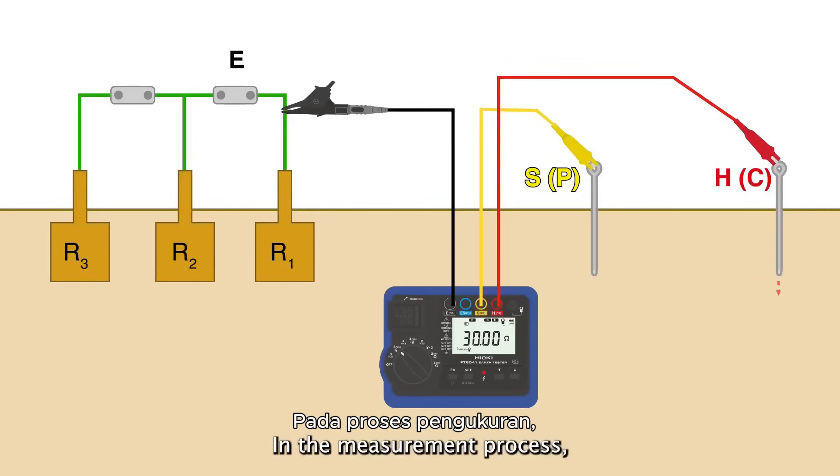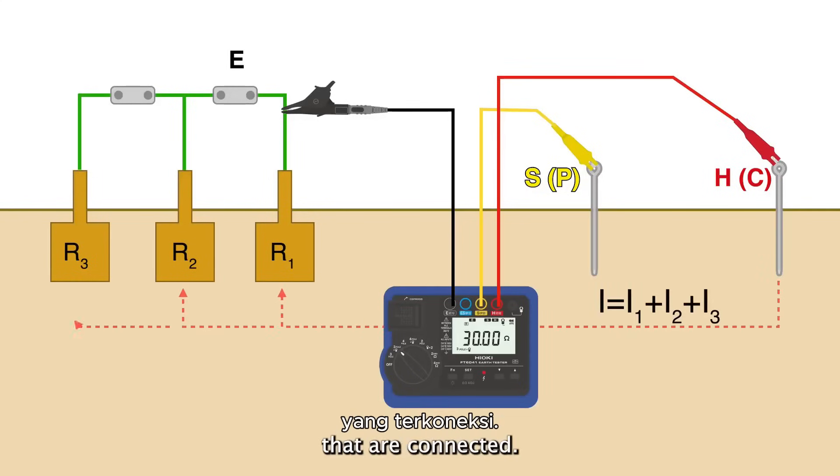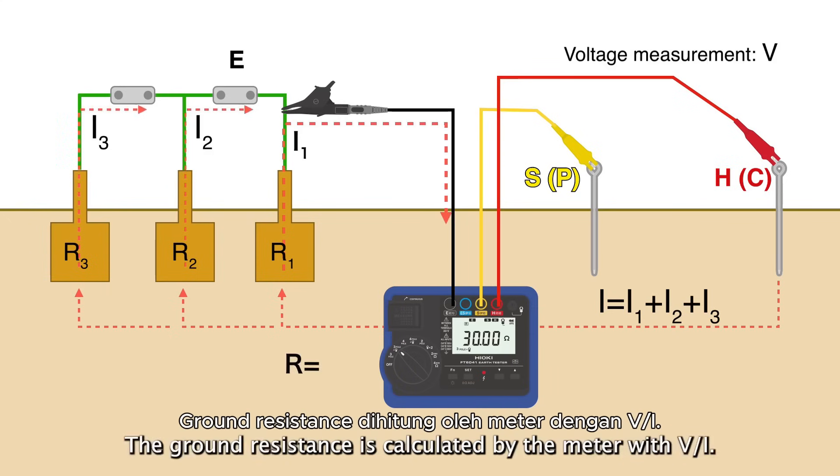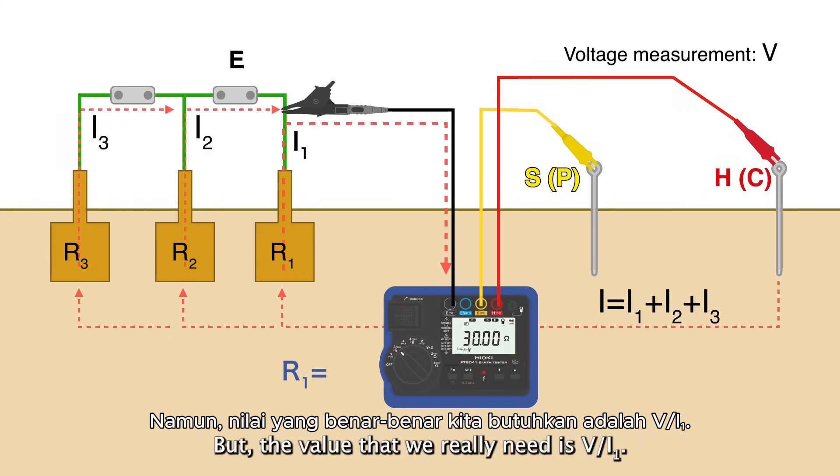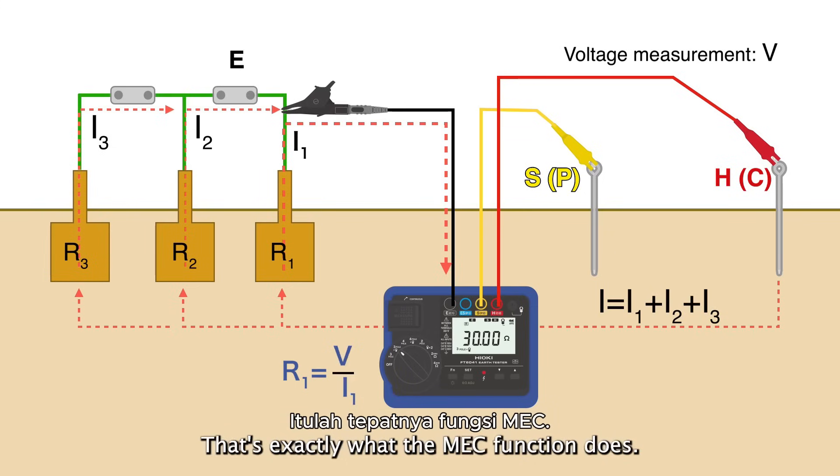In the measurement process, the current flows through all the grounding electrodes that are connected. The ground resistance is calculated by the meter with V over I, but the value that we really need is V over I1. That's exactly what the MEC function does.